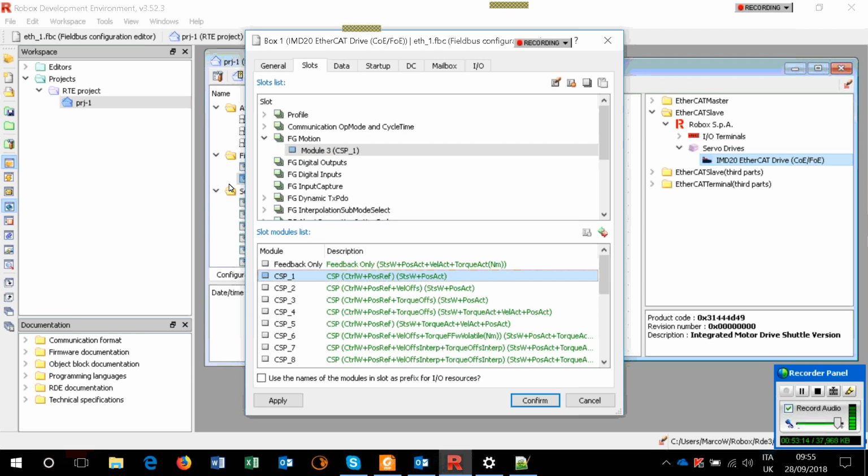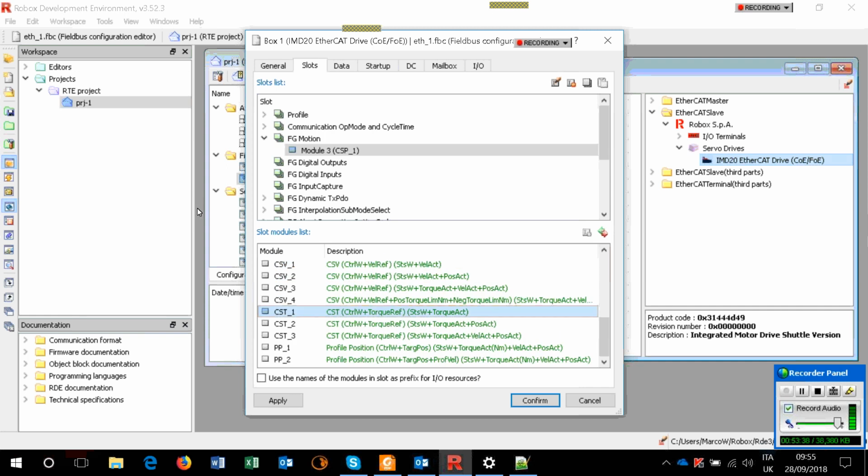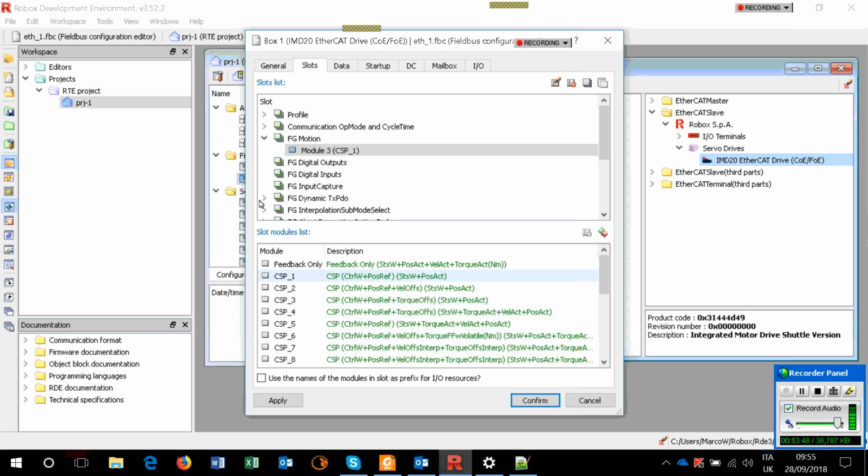And we have this one. We have control word and position reference given to the drive, and the status word and actual position returning from the drive to the controller. This is the way we control it. We may choose which one to have according to the drive you have, to the specifications, to what the customer needs, and so on. You see, we have a lot of possibilities of position control, speed control, torque control. Today, we just don't care about this, and I hope you will almost never do this.